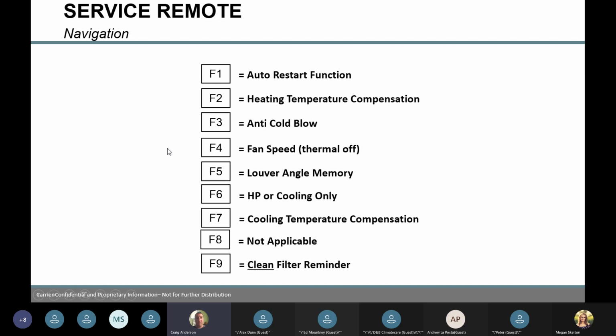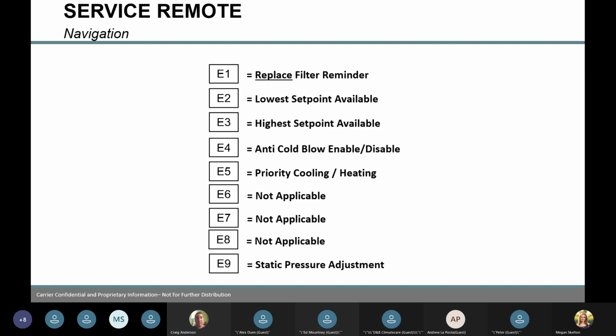So that's what we can do in the background of your thermostat or your remote control as well, like your parameters on a standard Honeywell stat. Highest set points for cooling, lowest set points, stuff like that, also that we can change on those parameters.